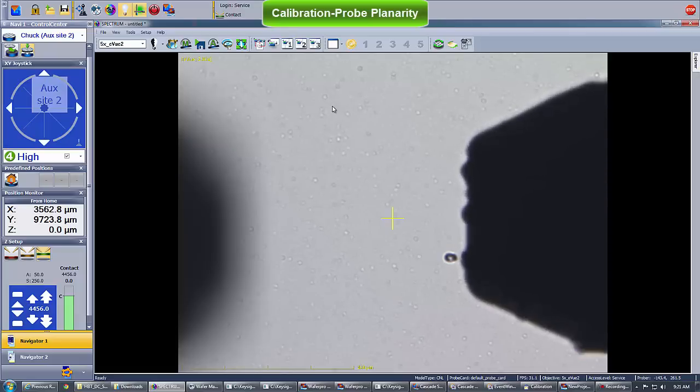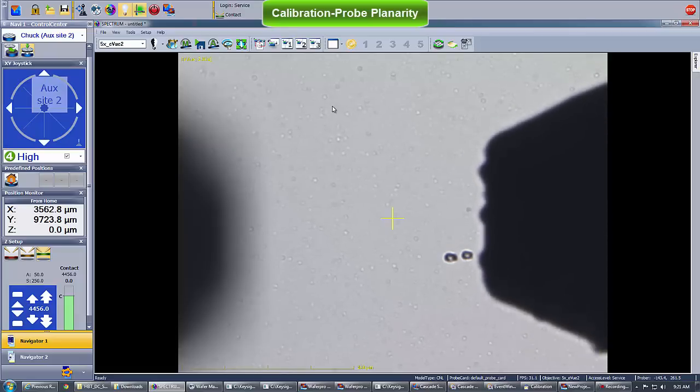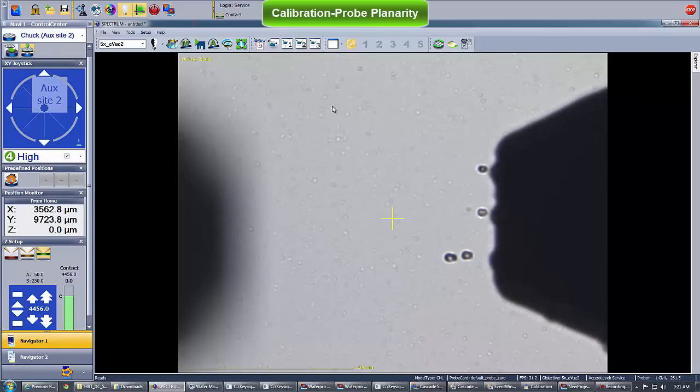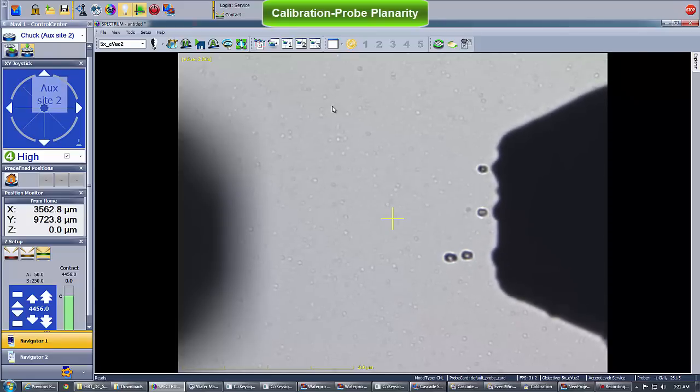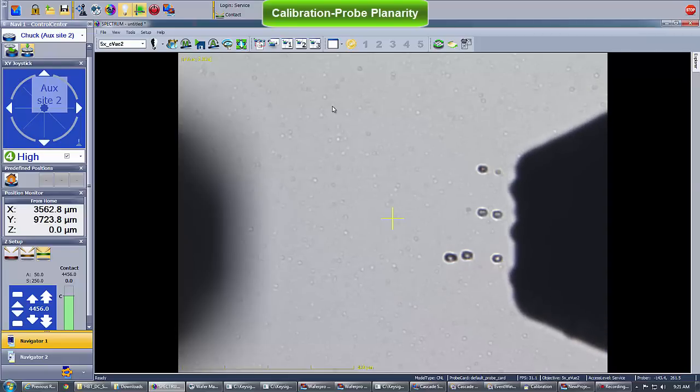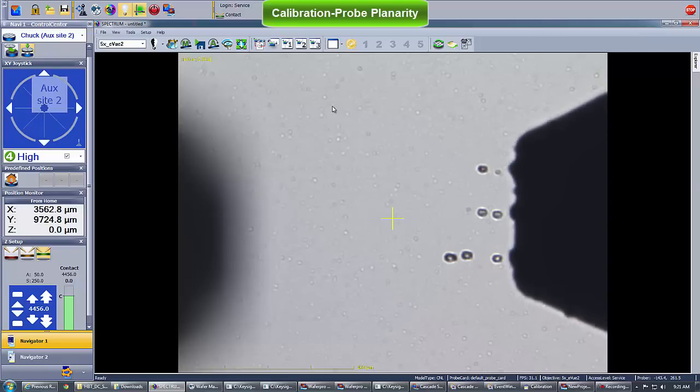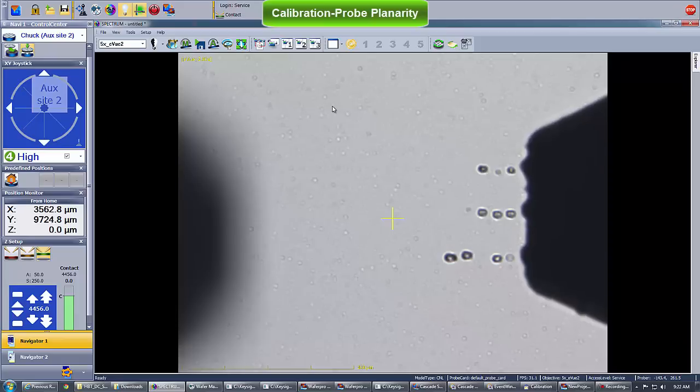By manually adjusting the probe positioner, we rotate the probe as necessary. After each adjustment, we touch down and visually check the marks. We might need to repeat a few times until all tips make good surface contact.